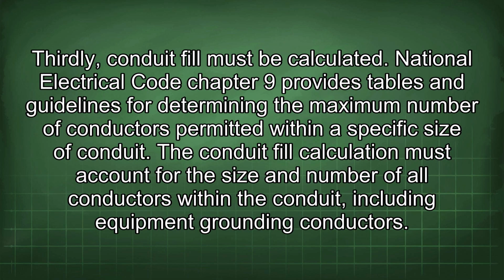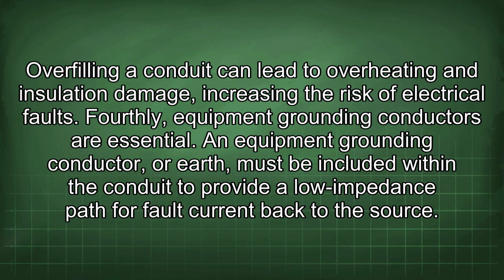Thirdly, conduit fill must be calculated. National Electrical Code Chapter 9 provides tables and guidelines for determining the maximum number of conductors permitted within a specific size of conduit. The conduit fill calculation must account for the size and number of all conductors within the conduit, including equipment grounding conductors. Overfilling a conduit can lead to overheating and insulation damage, increasing the risk of electrical faults.